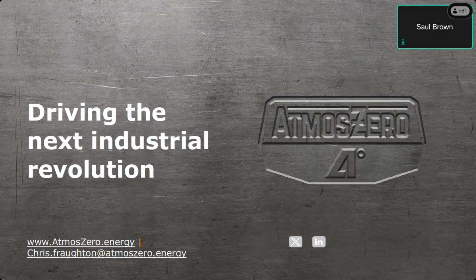Can the system respond to demand response signals from the grid? It can. The entire system can be remote monitored and remote operated. It turns on and off very quickly. From a warm start, you're under 5 minutes to full pressure steam. And from a cold start, you're about 10 to 12 minutes to full pressure steam. So it is a pretty quick response time.